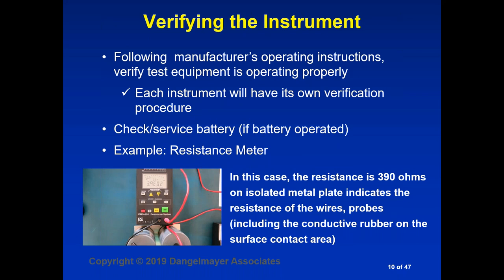First thing you do, before you even get into the area where you're going to do your verification measurements, is verify your instruments. Each of your instruments should be taken out of its case, and you should follow some procedure. Typically, the manufacturer will give you that procedure to verify that your test equipment is operating properly. I can't emphasize more: check or service the battery. Most of the instruments you're going to be using will probably be battery operated. And I would never go into a verification testing process without at least 10 batteries in my service kit. Typically, you find the instruments are going to use 9-volt batteries. Some may use AAs or AAAs, but make sure you have a supply of batteries with you, because in the process of doing compliance verification, these instruments do eat batteries, and you will need to change them in the course of a day. So make sure you have a good supply with you.